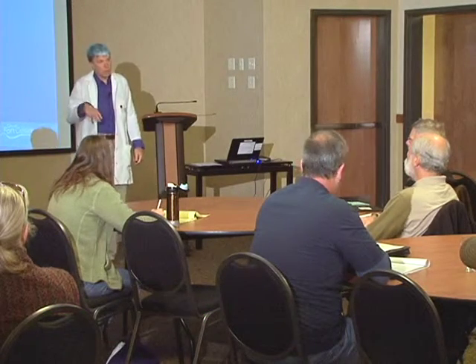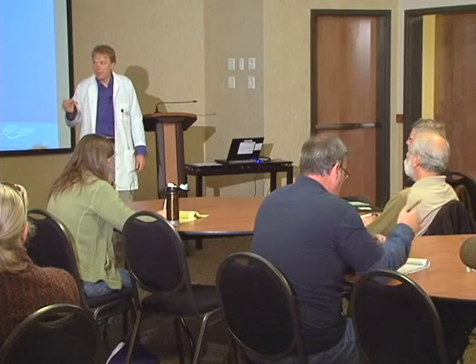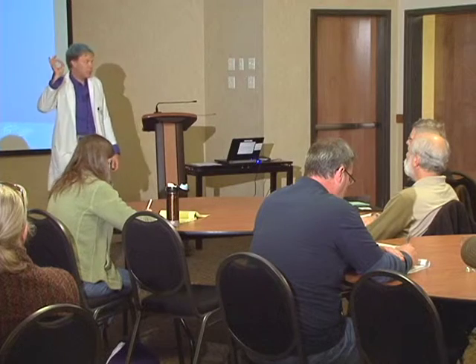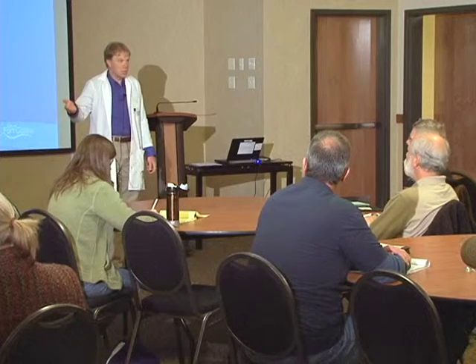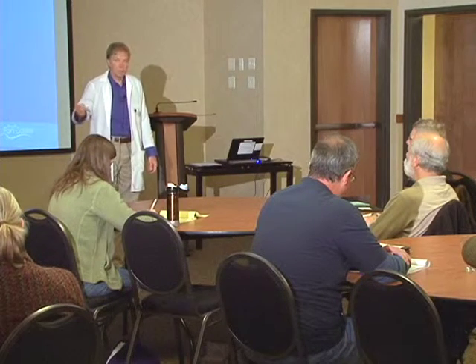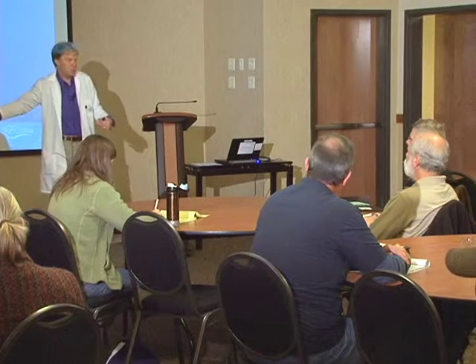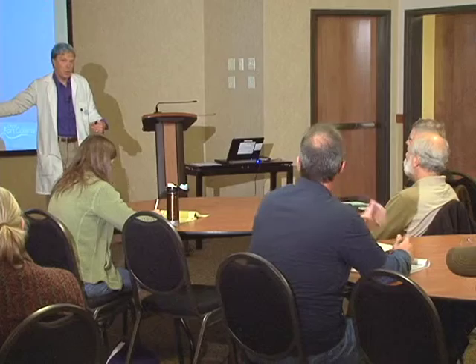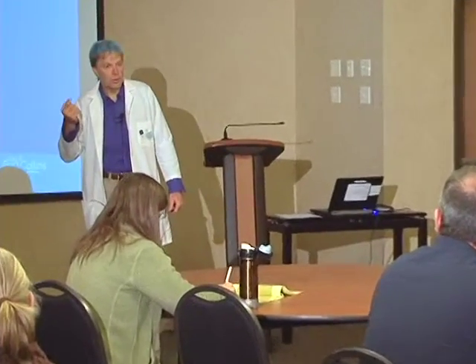So what's being talked about now is that for the last few years, we've primarily been upgrading the older T12 lamps, the 1.5-inch diameter lamps with magnetic ballast, to a current technology T8 lamp and electronic ballast. Well, even within the T8, you can actually jump an entire generation of T8 lamps and go to high efficiency ballasts with high efficiency lamps, higher color rendering and lumen output lamps, and essentially skip a whole step in there.